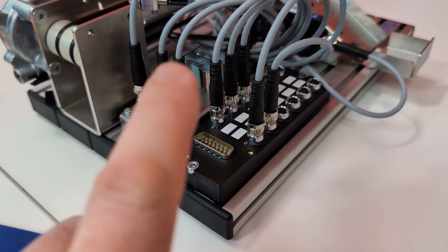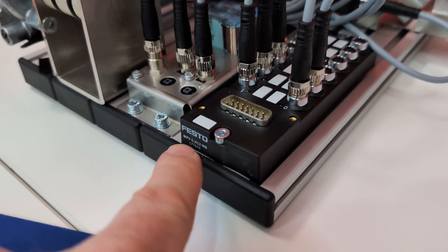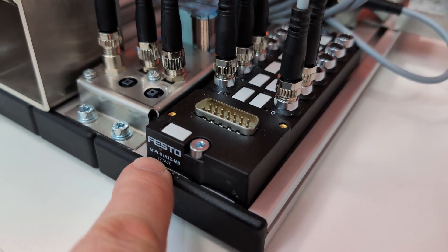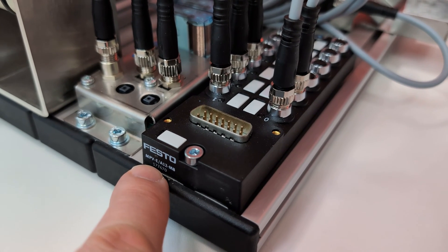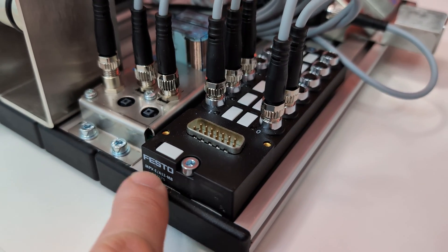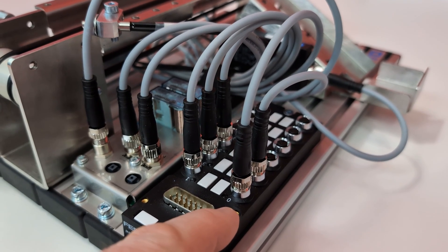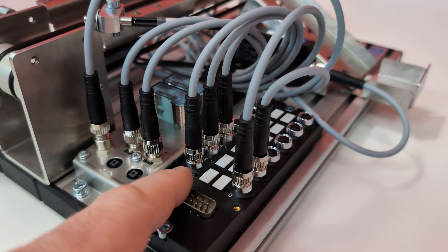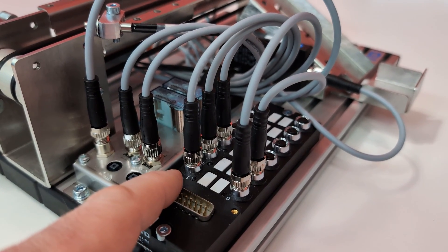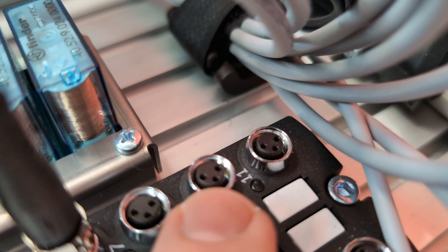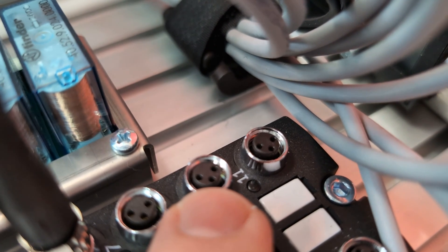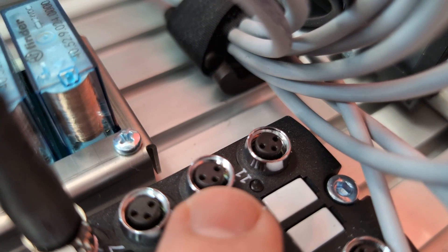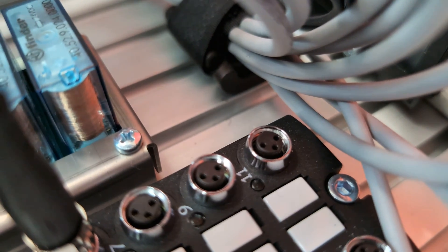All your connections come to this breakout module and this is a Festo MPV-E-A12-M8. Your even numbers are going to be your inputs and your odd numbers are going to be your outputs. Looking a little closer these are what we call M8 connectors and these are very standard sensor connectors and this one has three pins.